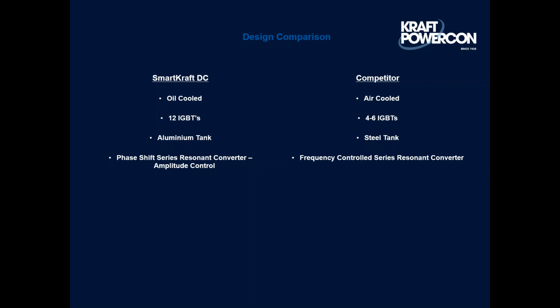Most of the others are using a steel tank. The key item is we have a phase shift resonance converter. That's a big, long technical term, so basically say an amplitude control. All the others on the market are using a frequency control, where they just vary the width of what current conducts, and it's difficult to turn off. So on very high current spikes, say in sparking, where you have poor grounding because it could spark anywhere in that precipitator, you could have some very high transient voltages getting back into the control cabinets and causing failures. In our technology, we're using an amplitude control, so we are actually controlling current. Current can never inrush or go to extreme values, and if there's an issue, we turn the current off. So once you turn the current off, there is no high transient spike going back into the system.